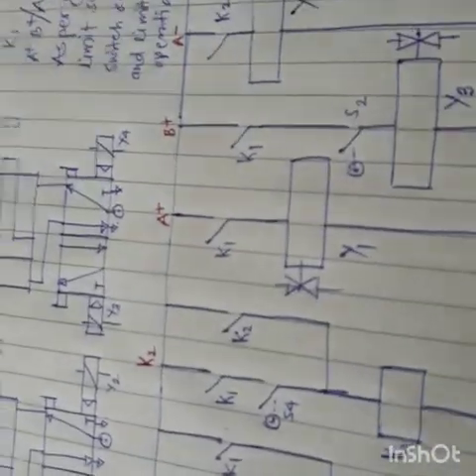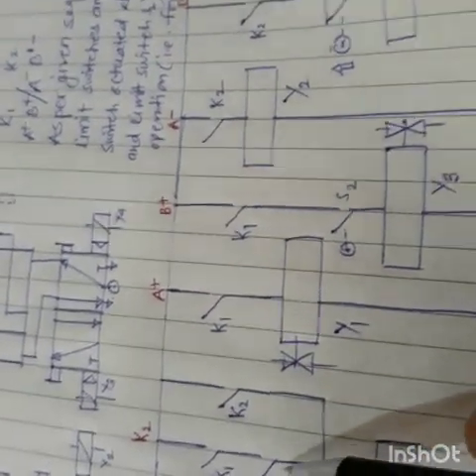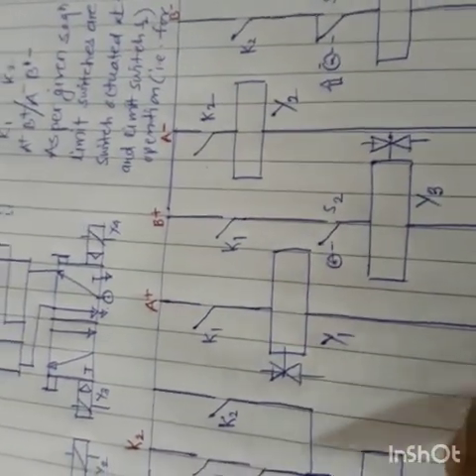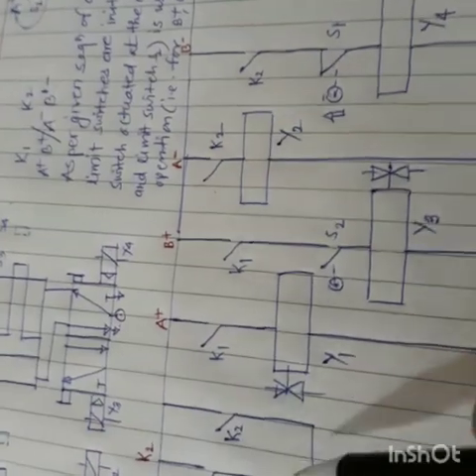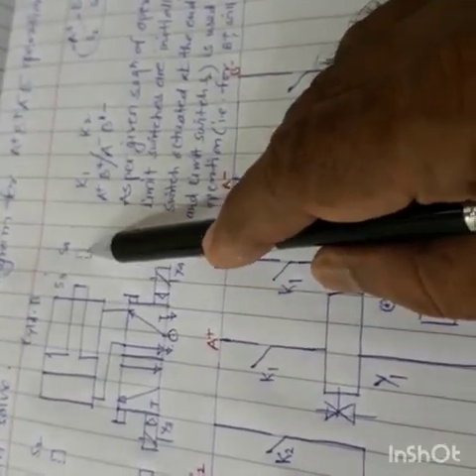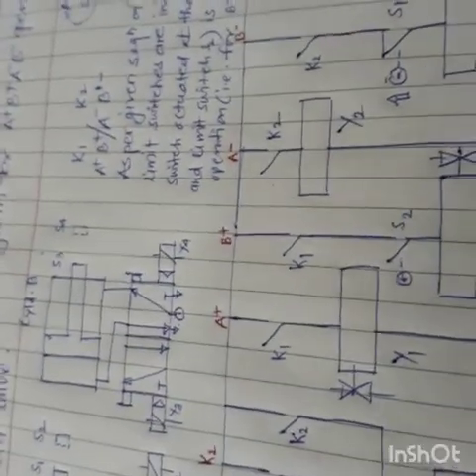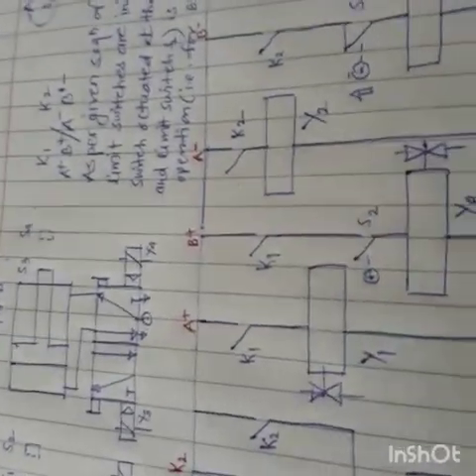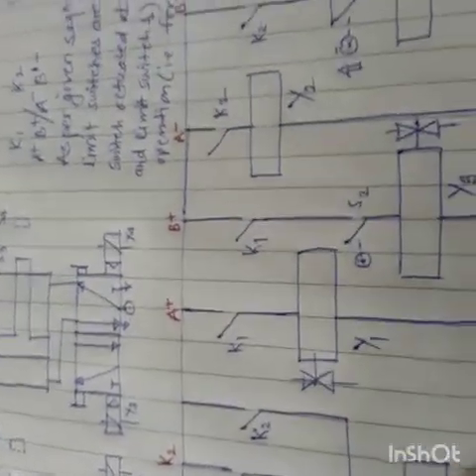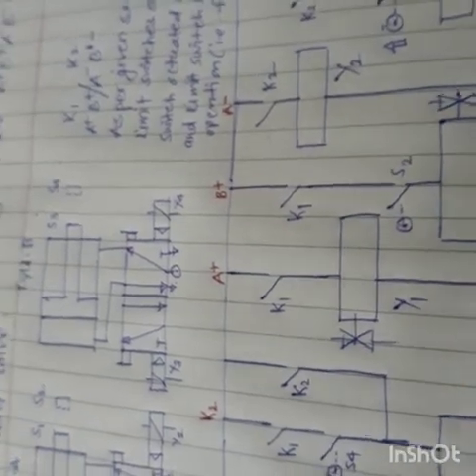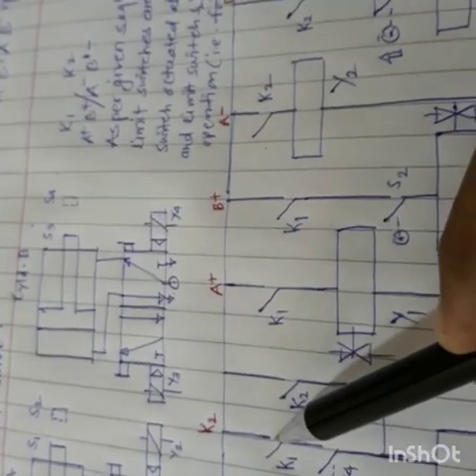Now for K2: K2 is the relay for group number 2. We draw the K1 relay switch of the first group, then S4, which is actuated at the end of the last operation of the K1 group — that is B plus. Then as usual we include the latching and relay K2. You can see: if this button is pressed, K1 is closed, S4 is closed, K2 will energize, and contacts related to K2 will also close.